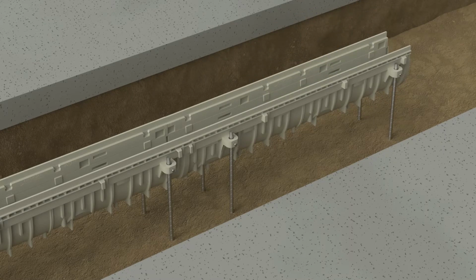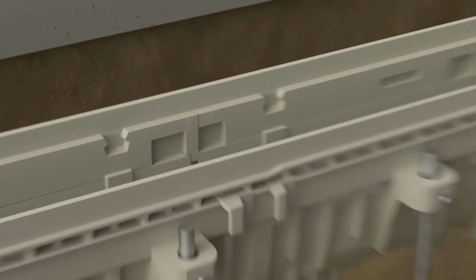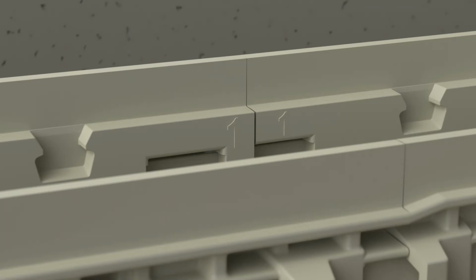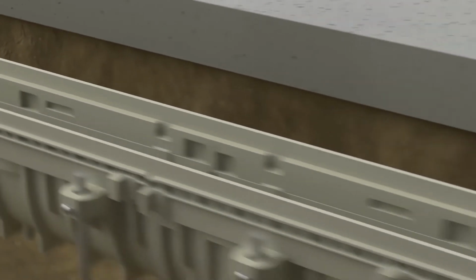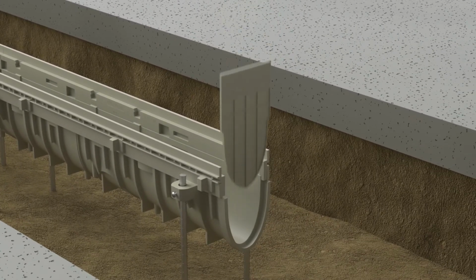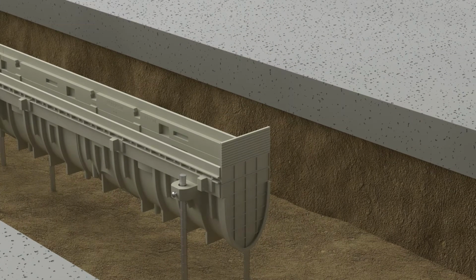Pro Plus trench drains with slope feature a unique numbering system inside each channel to help guide you through the installation process. If the numbers at each channel joint match, you know it's being installed correctly. When the last upstream channel is leveled and secured, install the end cap in the groove. Make sure to snap the top of the end cap to be flush with the channel.